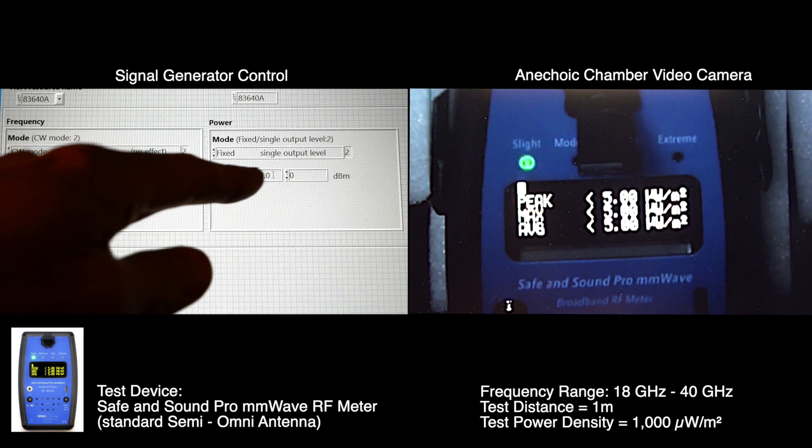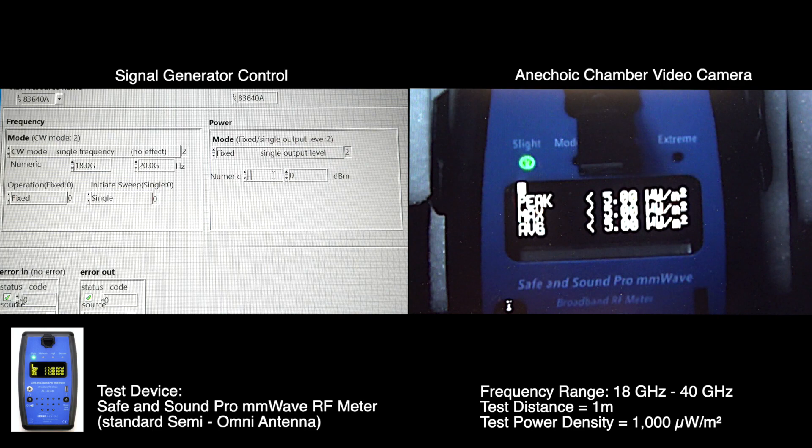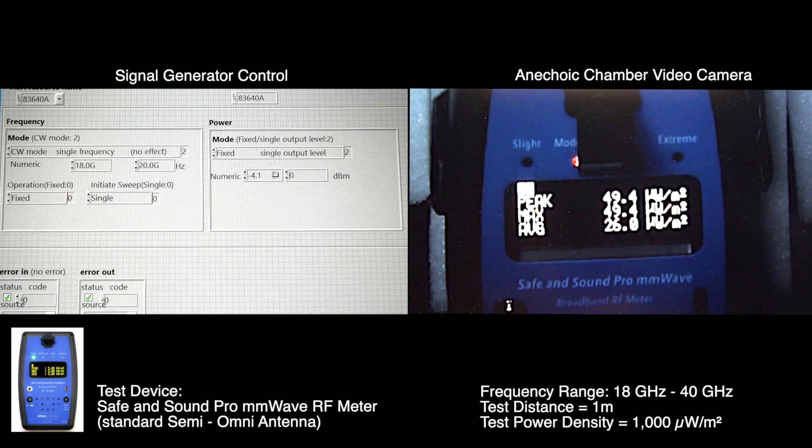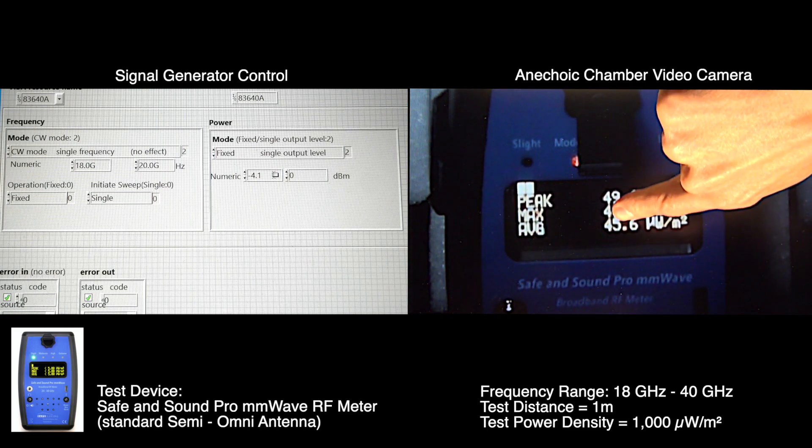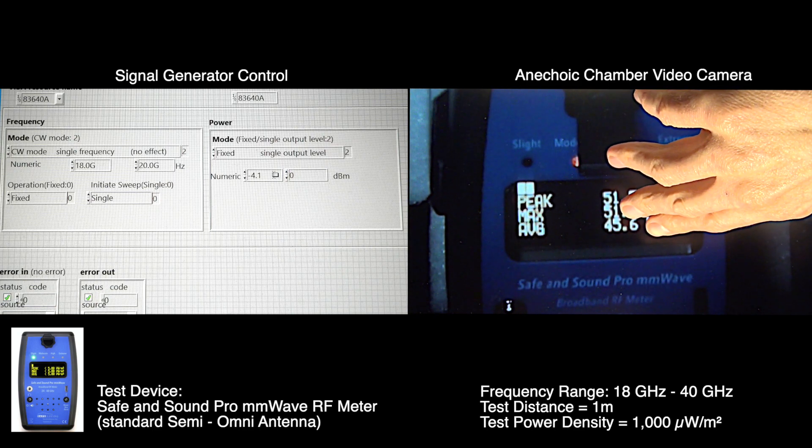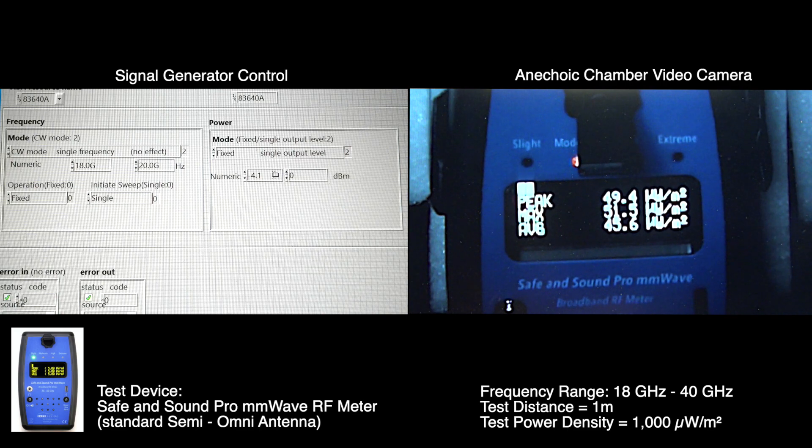I'm at 18 gigahertz and from previous calibration run with a calibrated power meter and a calibrated antenna I know that at 18 gigahertz I need to have a signal generator power of minus 4.1 dBm. So here it is. I turn on the transmitter and I'm going to look at the average for this test. Now again we're rating this meter from 20 to 40 gigahertz. So right now looking at average I'm at 45.6 microwatts per square meter.